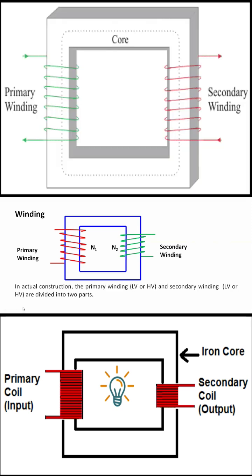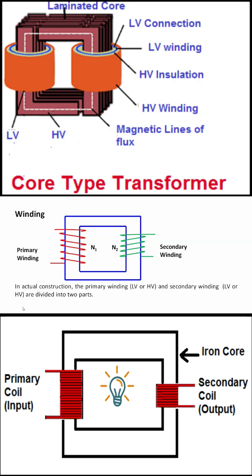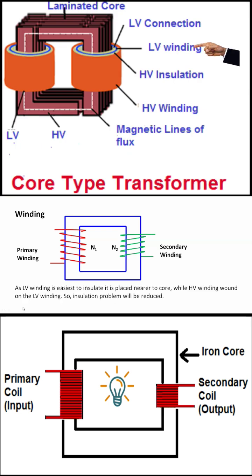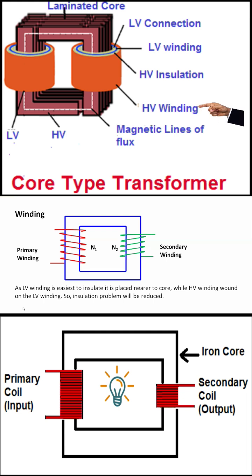In actual construction, the primary winding — LV or HV (low voltage and high voltage) — and the secondary winding — LV or HV — are divided into two parts. Since the LV winding is easiest to insulate, it is placed nearer to the core, while the HV winding is placed along the outside of the LV winding, so the insulation problem will be reduced.